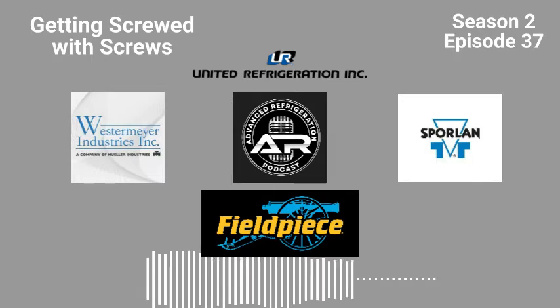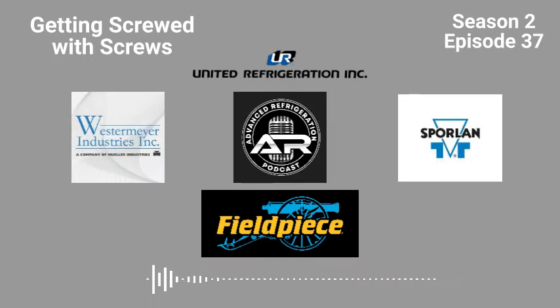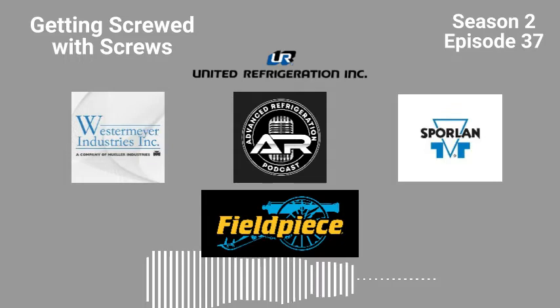So I finally figured out it's missing the forward run. I find the relay. Okay, trace it back. It's tripped on high pressure. Okay. I push the high pressure switch. Ramps up, gets to 30 hertz, and then ramps up, gets to 60 hertz. I hear that it sounds like shit. This doesn't sound right. It's pulling like 60 amps. All of a sudden, it shuts down again. I push it again. Starts back up. It runs.